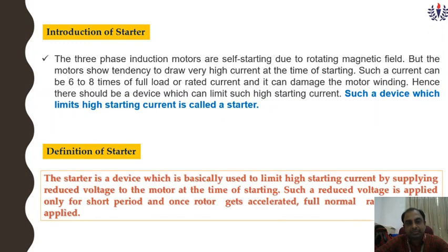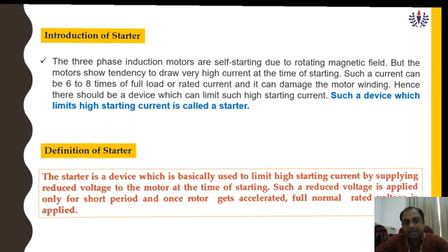What is the definition? The starter is a device which is basically used to limit high starting current by supplying reduced voltage to the motor at the time of starting. Such a reduced voltage is applied only for a short period, and once the rotor gets accelerated, the full rated normal voltage is applied.